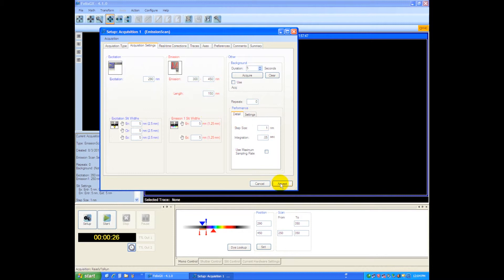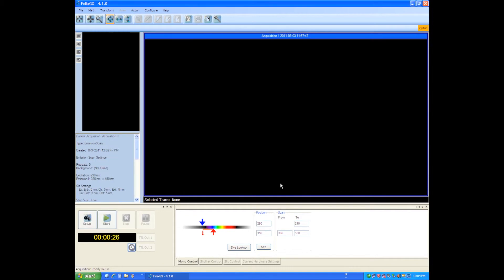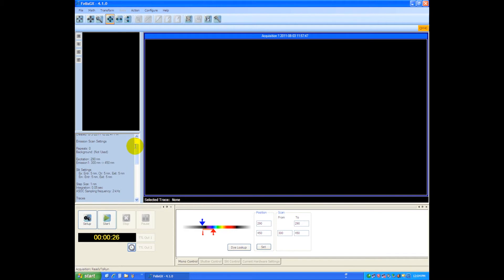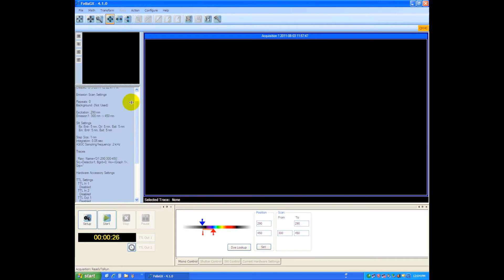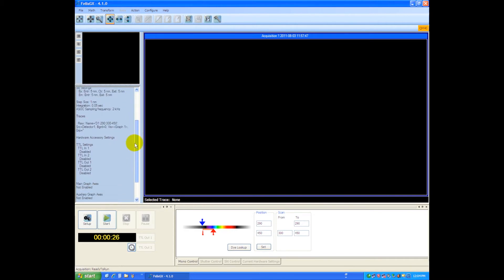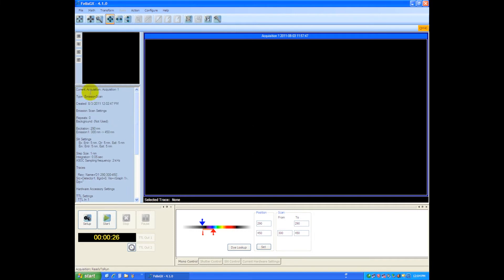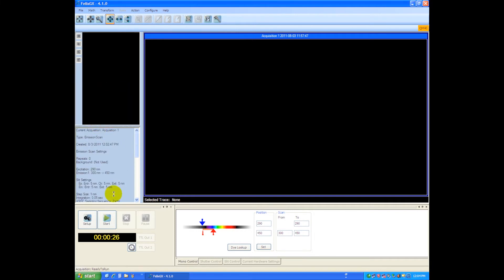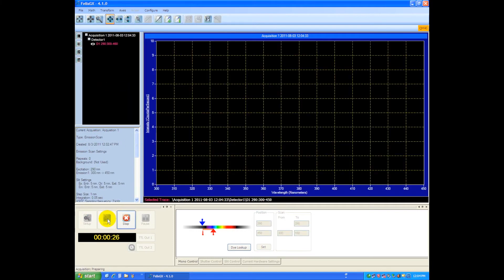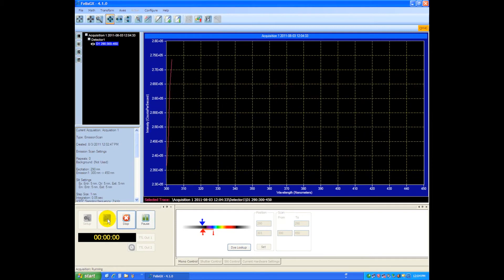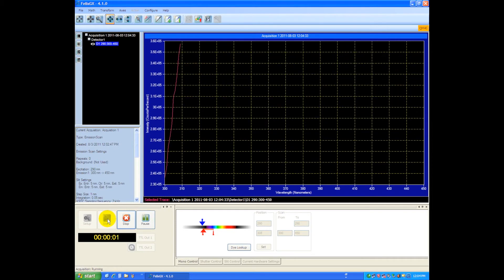So we just say accept and we simply click on the start button. If you want to verify your settings, you can look through this text output which will tell you all the parameters that you set up. So we'll click start next. The monochromators will prepare and then the scan will begin.